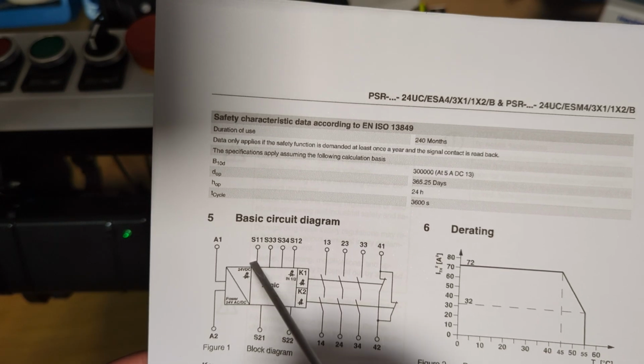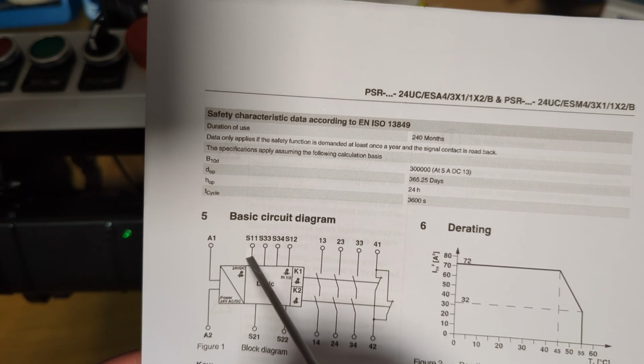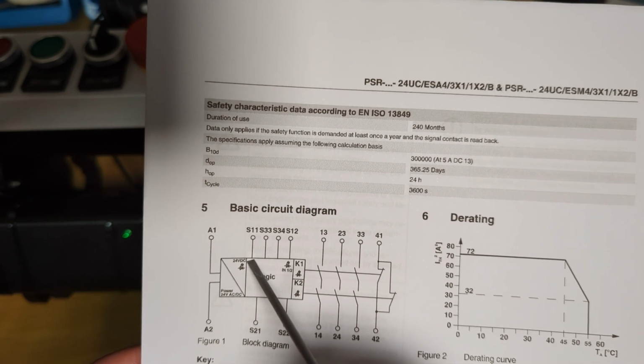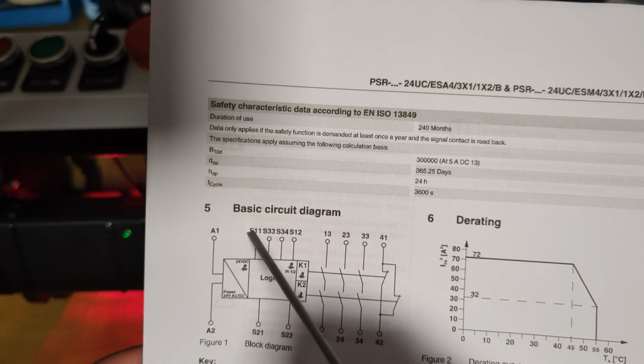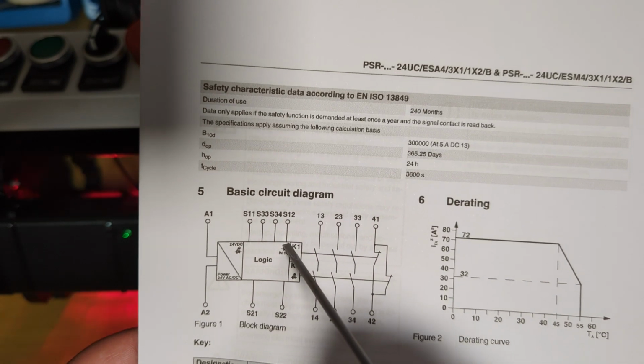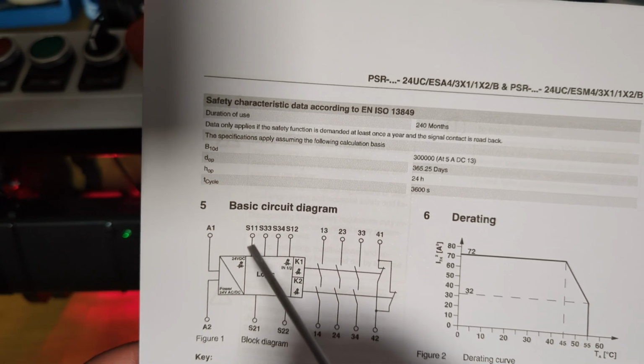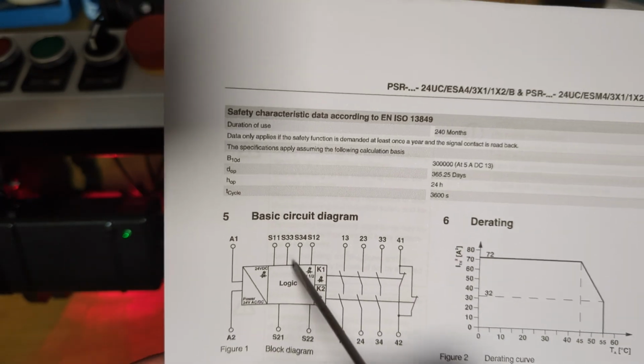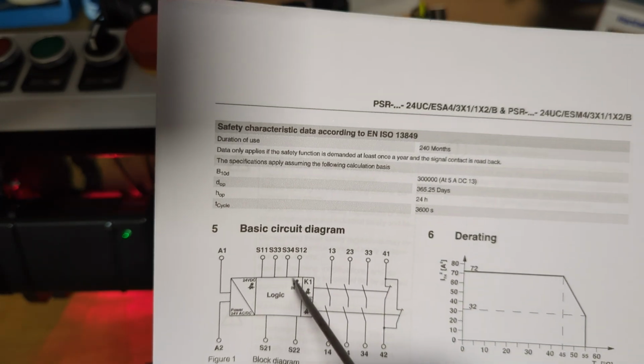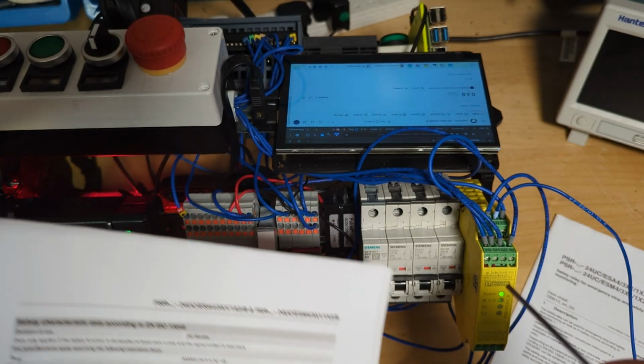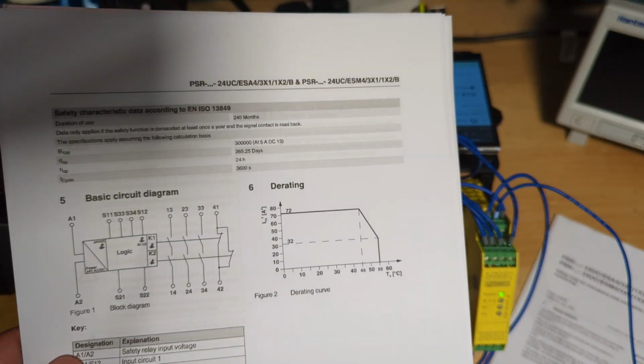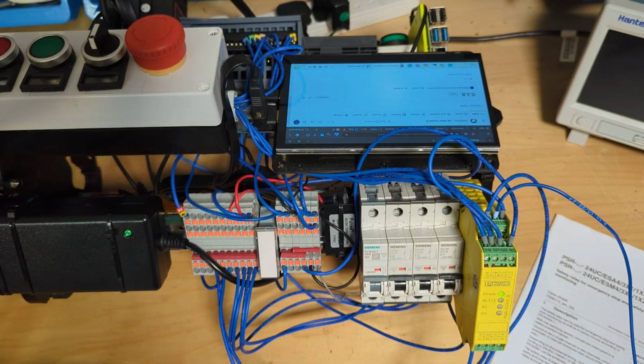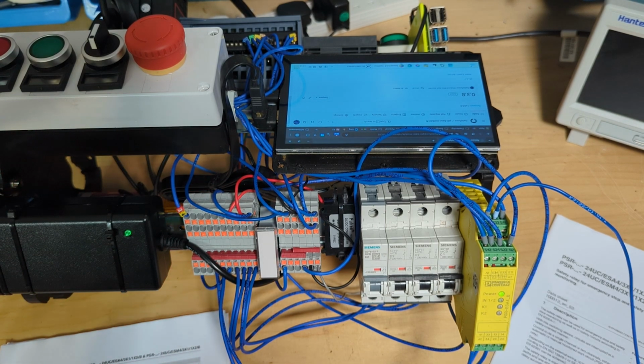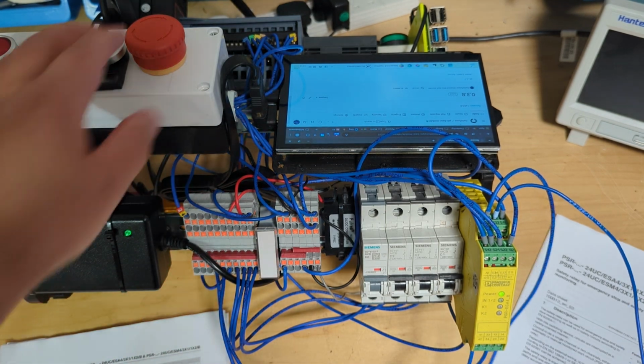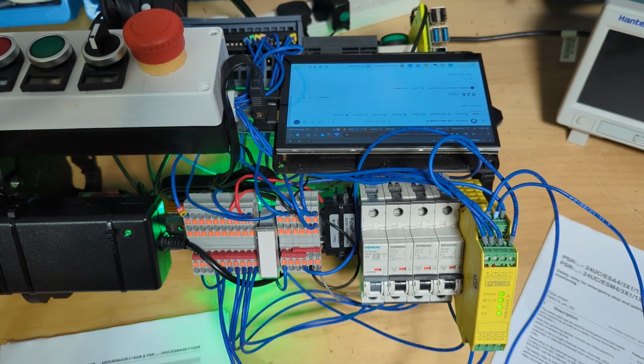Some of them will send out a pulse width modulated signal, a square wave, a triangle wave. It'll send out a certain modulated signal on S11 and expect to see it back on S12. It knows how long it expects to see that back, and what type of signal. So if you manipulate that signal in any way, it will go, oh, I've got a problem, and then not work. So some safety relays do have fancier detection than others, so just be aware of that.